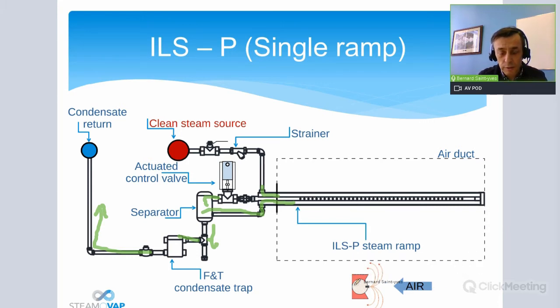So if we look at the section view of the distributor, you see the two chambers, and some will have a wall here. Our design is made so that the two chambers are separated by the tube that is used for the steam humidification. Okay, so that's what Armstrong launched in the last century, and that was the basic design. What their patent is, is to have all this in one component. Which all the other manufacturers now are doing in two components. One component for the steam separator and one for the steam valve, which is in fact much more flexible for connection, but also for the different capacity that you can have and for control. Okay.